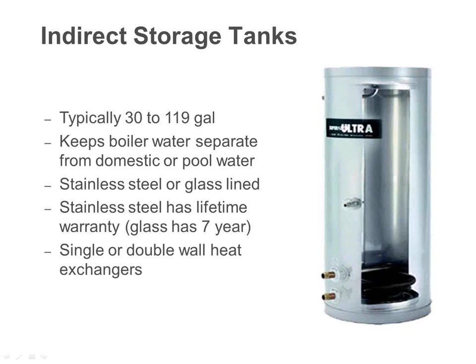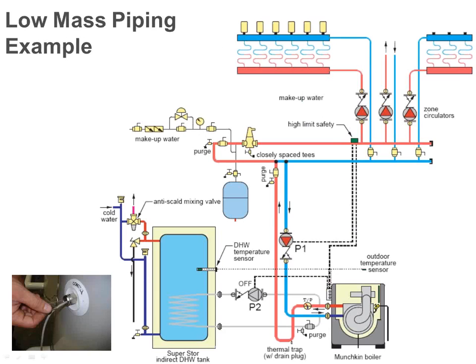If you're talking residentially, what this does is basically now you have a lifetime warranty water heater. Talking commercial, basically you're at about a 7 to 10 year warranty. What you do have is a super insulated, think of it as a thermos bottle, water heater. And it gets rid of that whole flue issue for the gas-fired water heater. We really wouldn't want to see you going electric just to make up that load. So it's very easy for us to do this off those condensing boilers. This shows you an example of it. It's not really complicated if you break it down, but there's that indirect domestic hot water storage tank over on the left, and then we have our boiler on the right side.